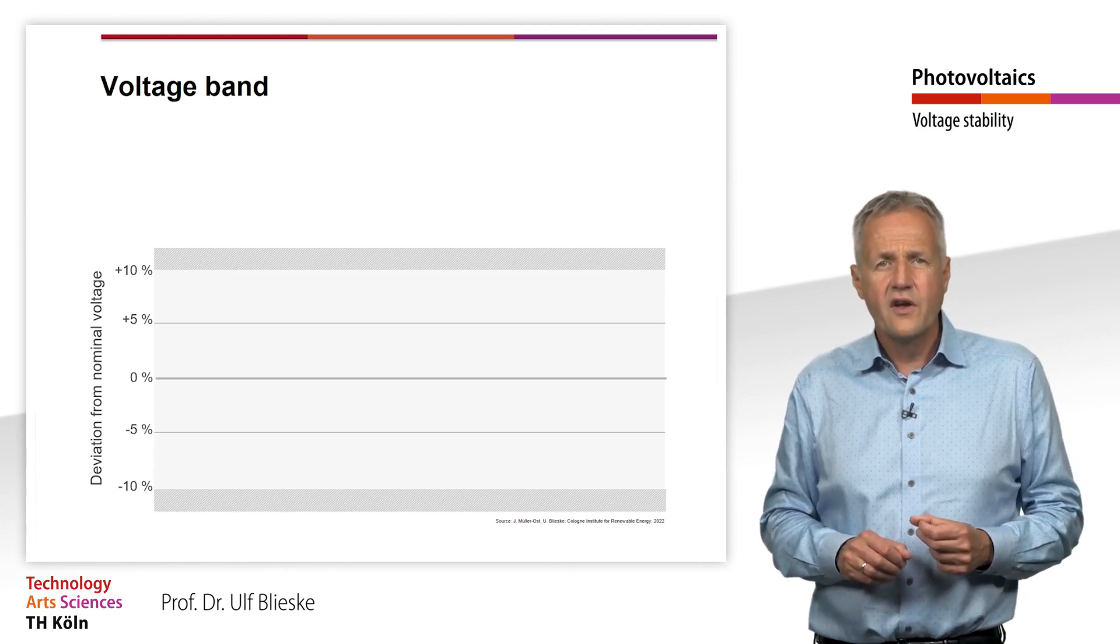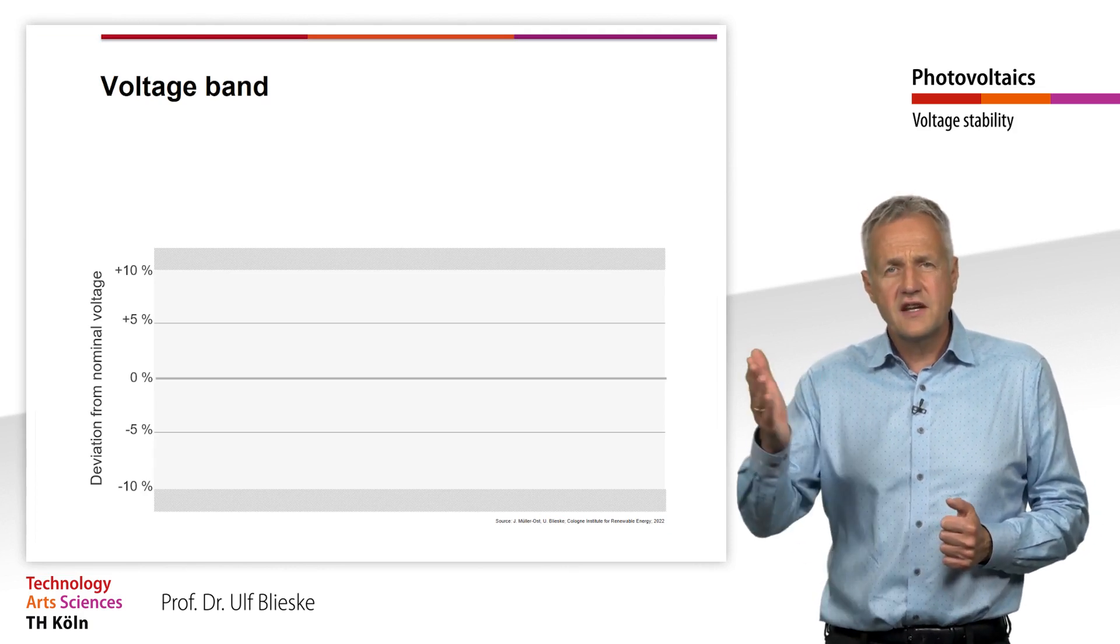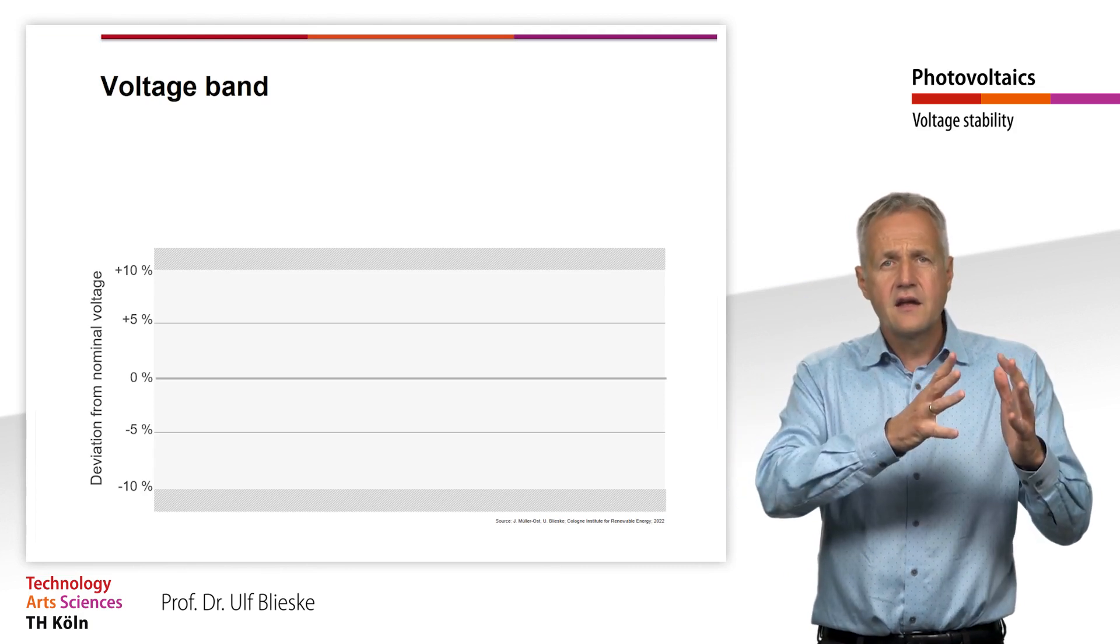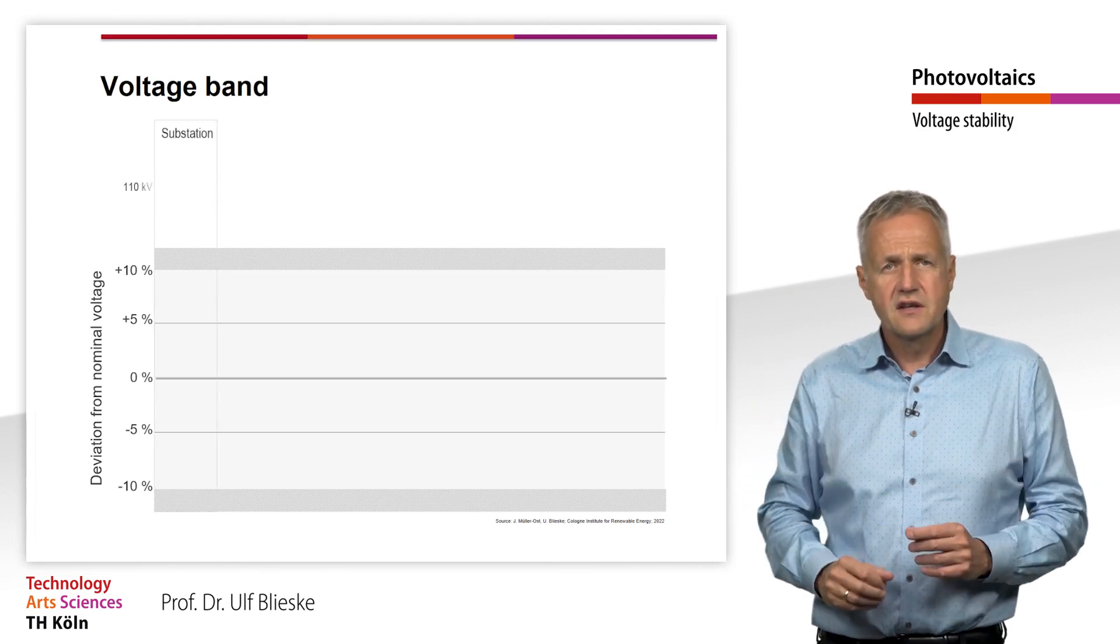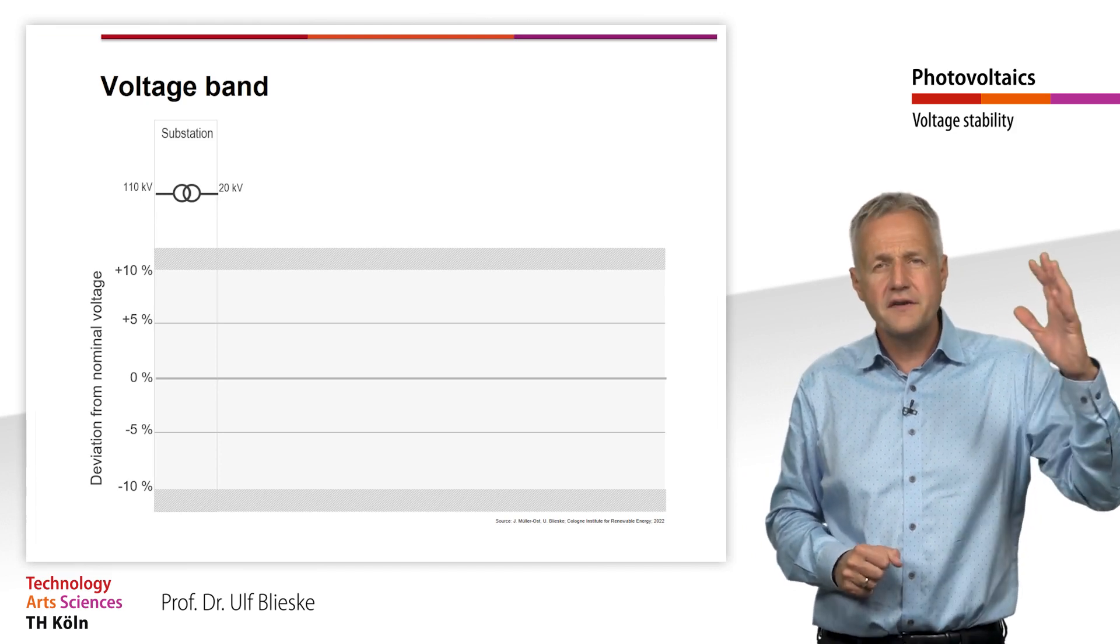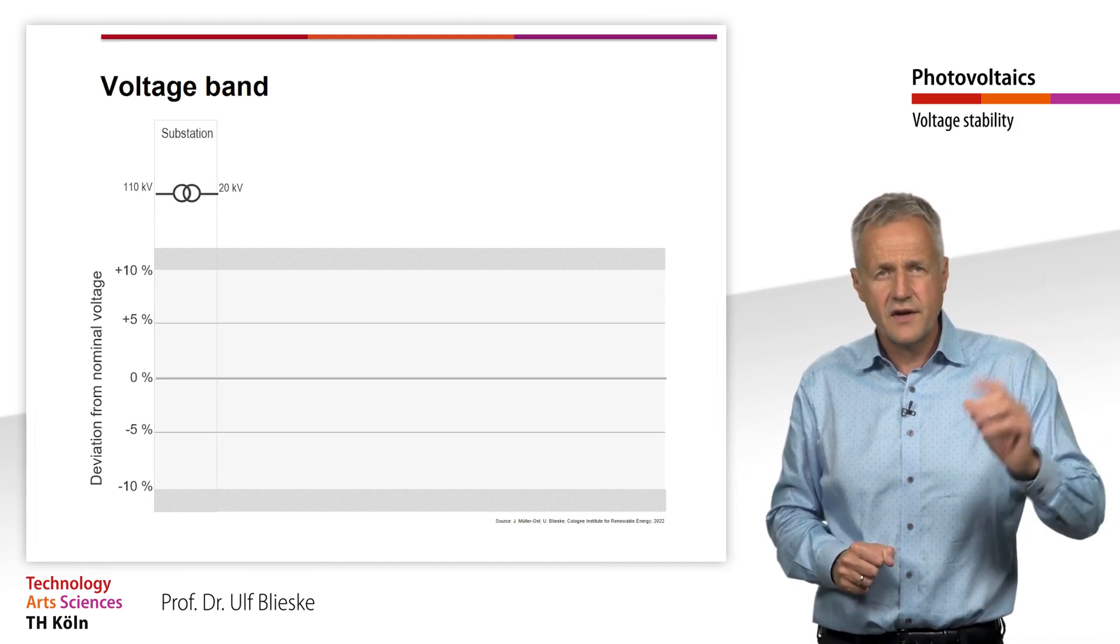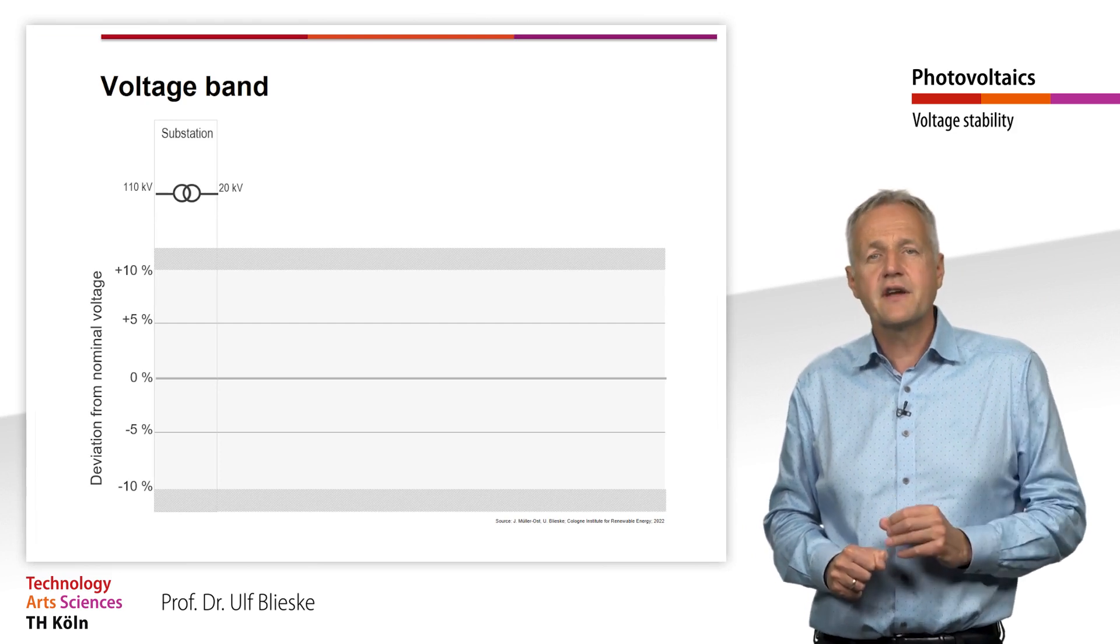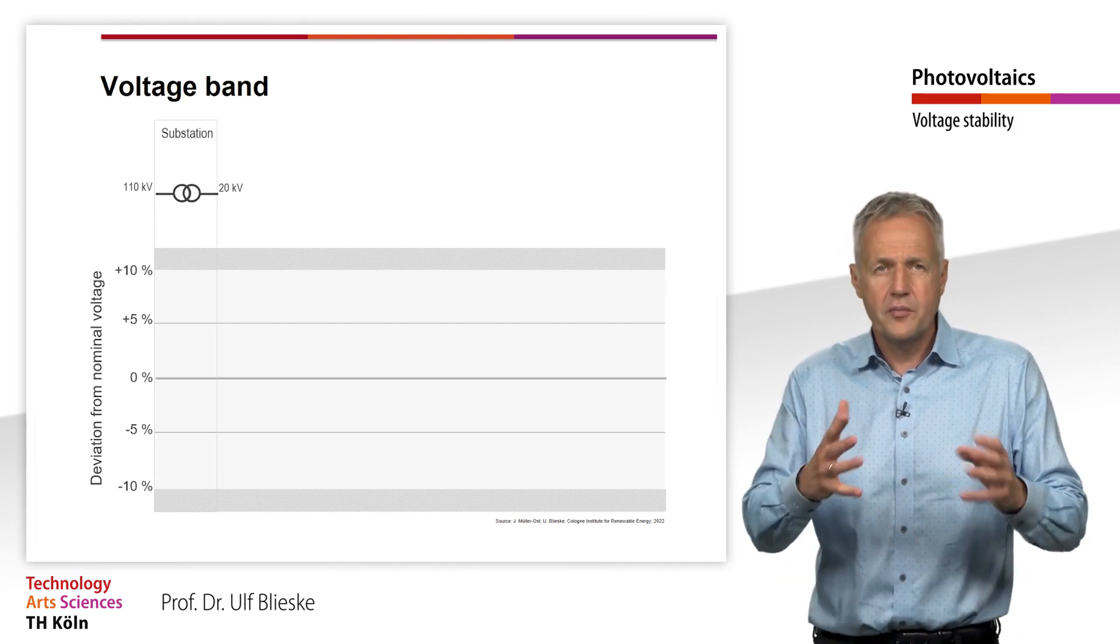First, we have the substation between the high and the medium voltage grid. In the German power grid, the voltage here is transformed from 110 kV to 20 kV in rural areas and 10 kV in urban areas.